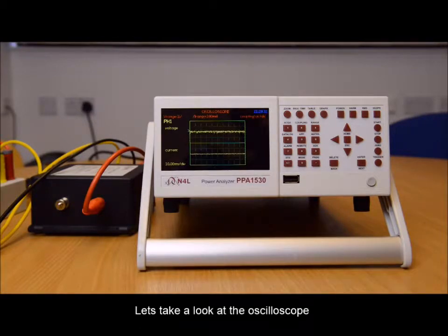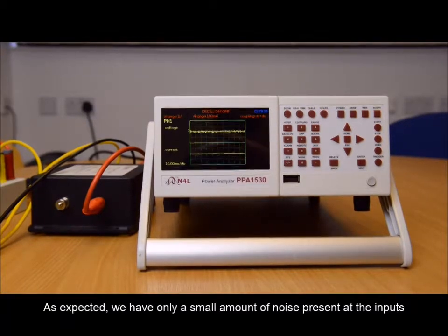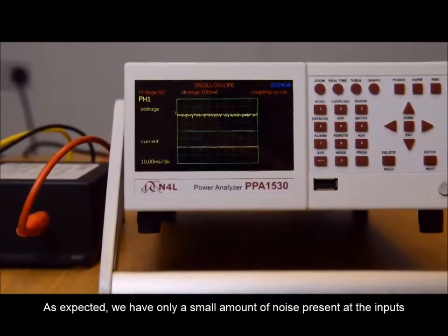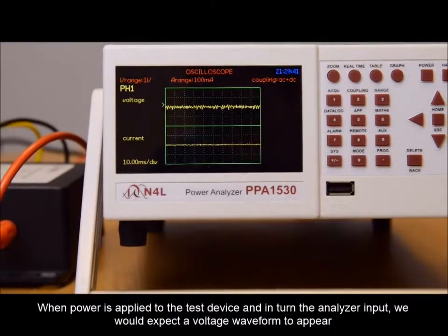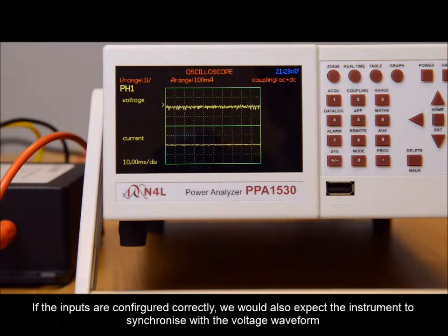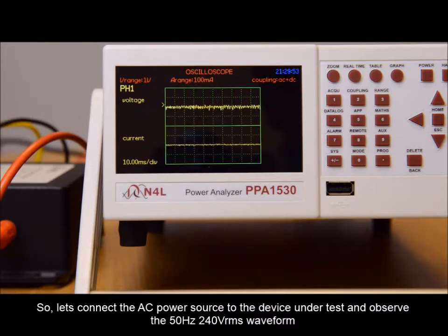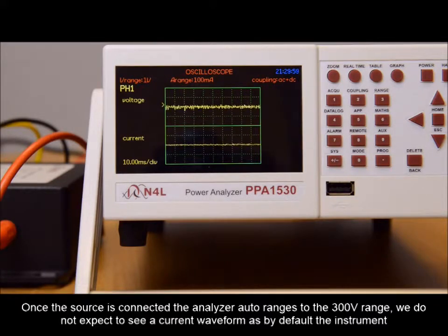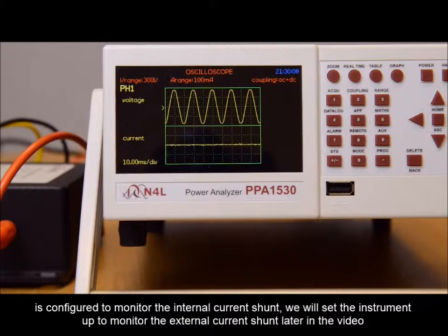Let's take a look at the oscilloscope. As expected, we have only a small amount of noise present at the inputs. When power is applied to the test device and in turn the analyzer input, we would expect a voltage waveform to appear. If the inputs are configured correctly, we would expect the instrument to synchronize with the voltage waveform. So, let's connect the AC power source to the device under test and observe the 50 Hz 240 volt RMS waveform. Once the source is connected, the analyzer auto ranges to the 300 volt range. We do not expect to see a current waveform as by default the instrument is configured to monitor the internal current shunt. We will set the instrument up to monitor the external shunt later in the video.